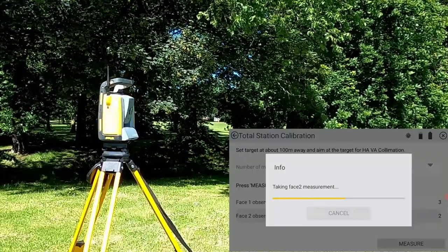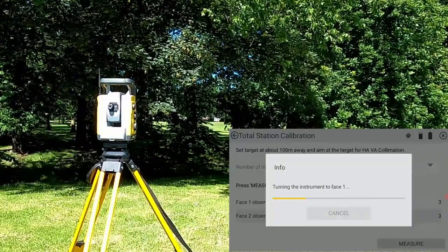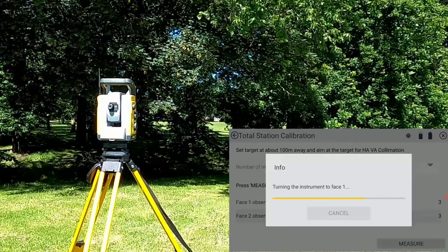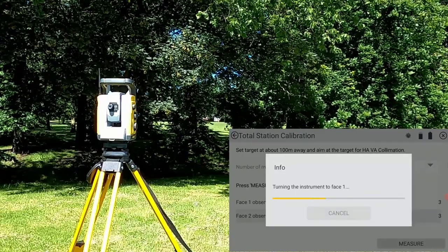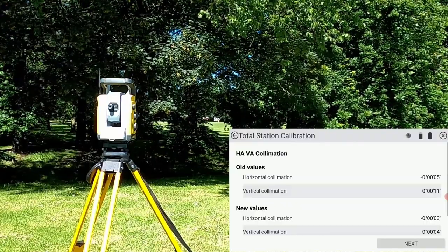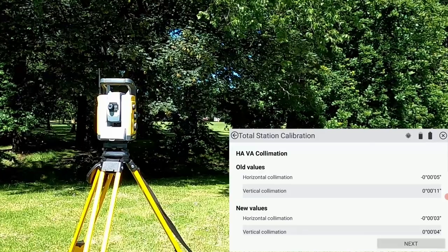When the final observation is taken, the instrument switches back to face one and it will compute the new horizontal angle and vertical angle collimation values.